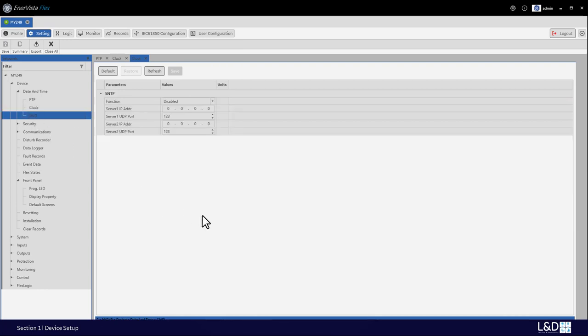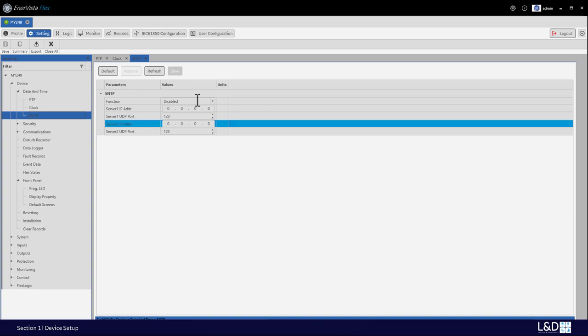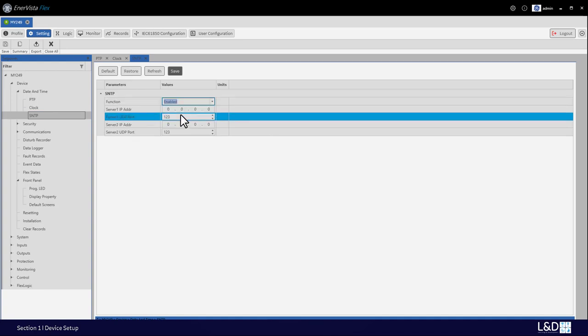SNTP stands for Simple Network Time Protocol, which is used to synchronize the clocks of computer systems over packet-switched variable-latency data networks such as IP. Relays accept time synchronization from up to two different SNTP servers. If SNTP is used to synchronize the relay, then the IP and UDP port for the main server must be configured along with the IP and UDP port for the backup server.